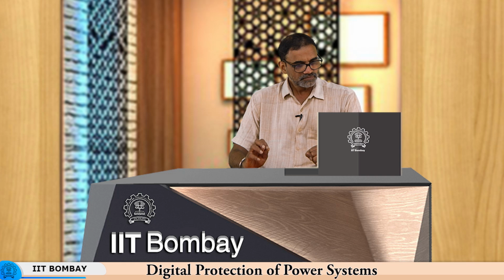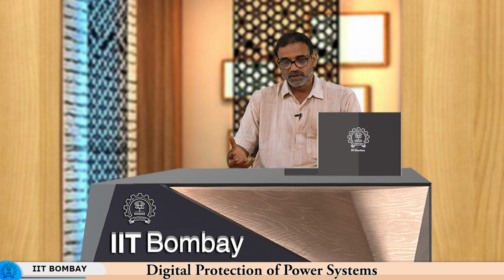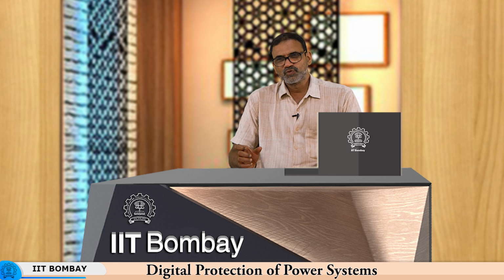So there are advantages like this. Plus, in earlier days, the relay could not store any data. Now, one of the major advantages of numerical relays is that it can store data. Whenever there is an event, a tripping, or some transient event, the relay's data storage is triggered, and you get up to about 5 cycles before the event and some after the event.